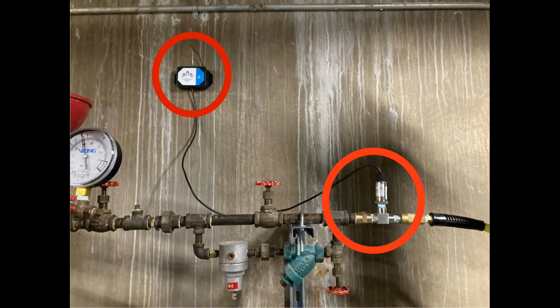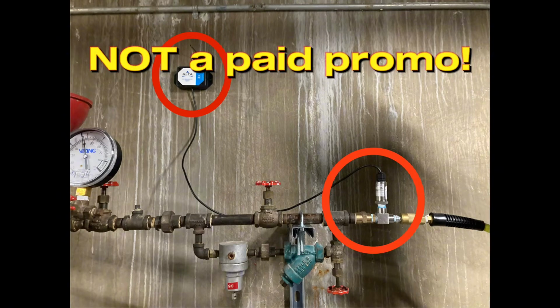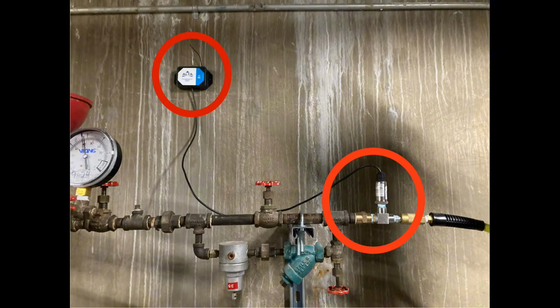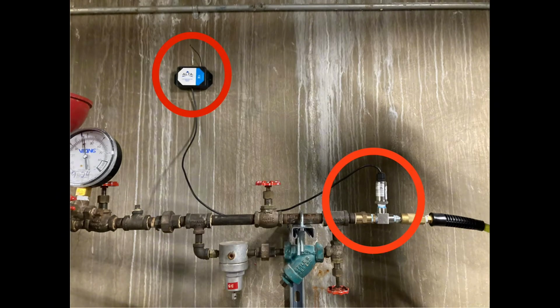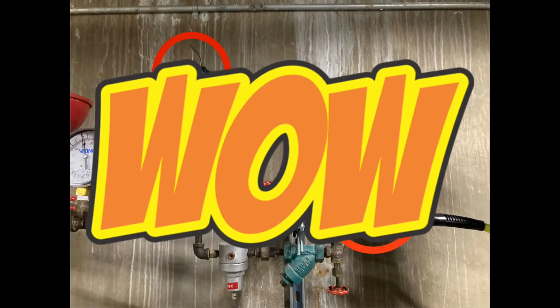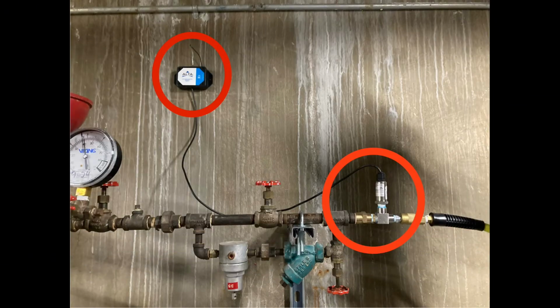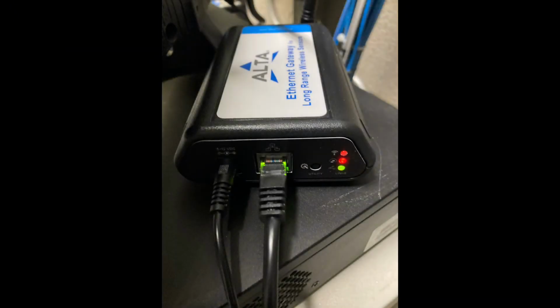We'll log on to our dashboard at imonnit.com, which is what we used. You pay a small fee, I think it's like 30 or 40 bucks a year, which isn't too bad. We looked into hooking it up to our BAS system for the building, but the local HVAC contractor we use wanted over $1,000 to install their own pressure sensor and run some 18-4 wire, which was too expensive for us. Altogether, I think we spent $700 at the most, so we saved ourselves almost $700, since they'd quoted us around $1,400.